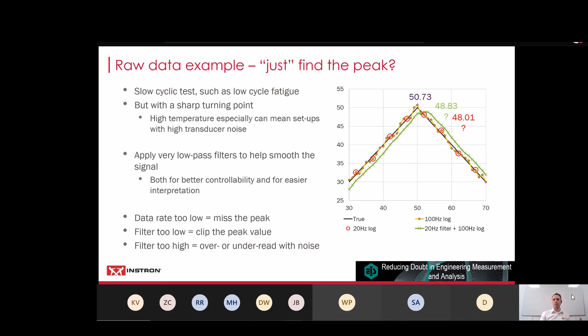There we go. Then, if we filter it and we're really smoothing lots of stuff out, we get the green line, but we've rounded the point off. Now we've clipped the peak value, so we're under-reading again. But if we don't filter very much, and we take basically the raw data, then we've got a bigger influence from our noise. And so are we under-reading? Are we over-reading? Or do we just bind that uncertainty into our measurement, into what we declare?